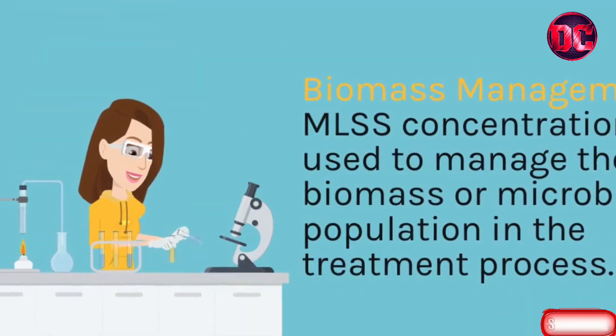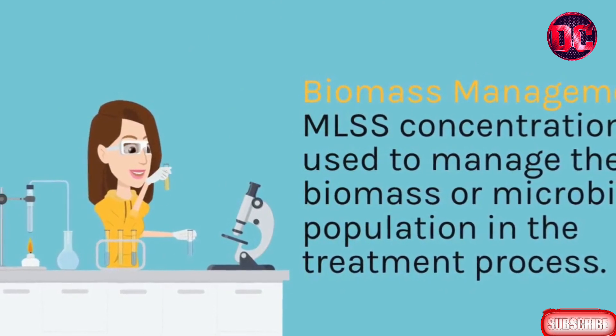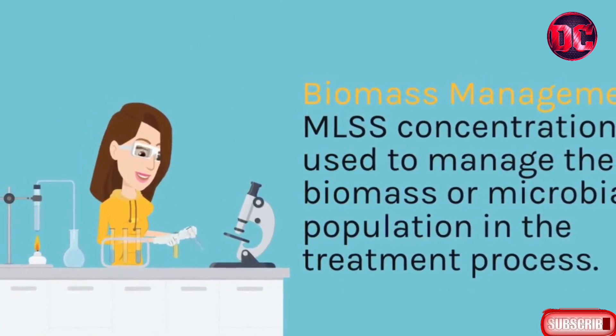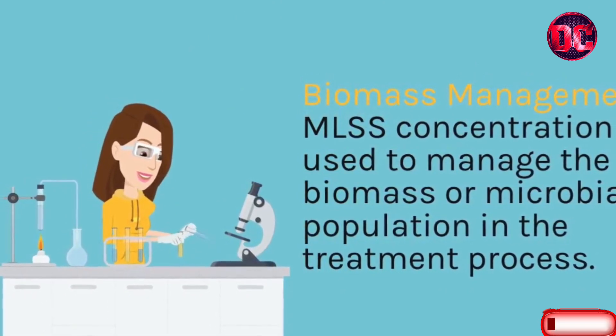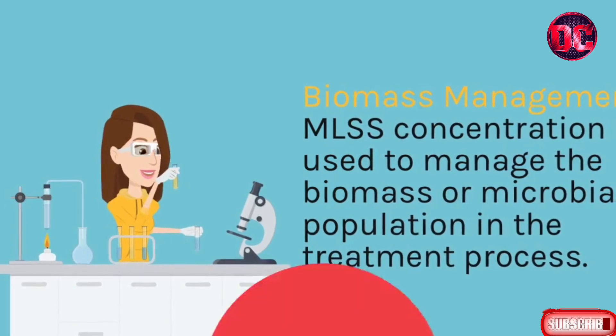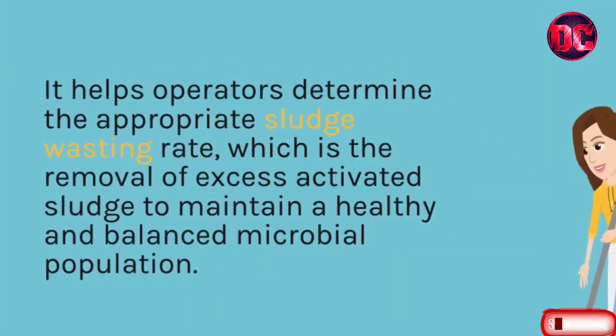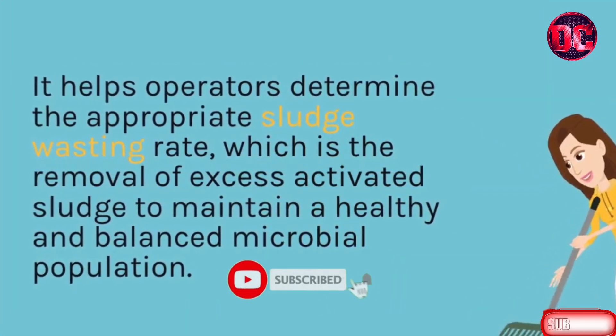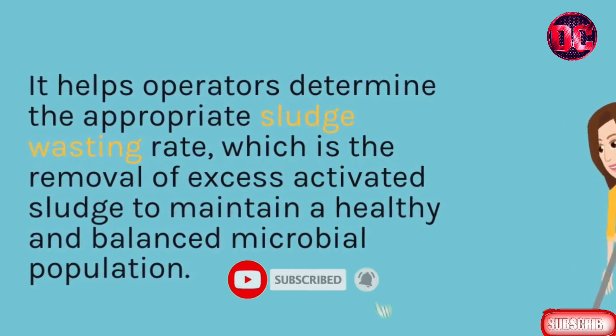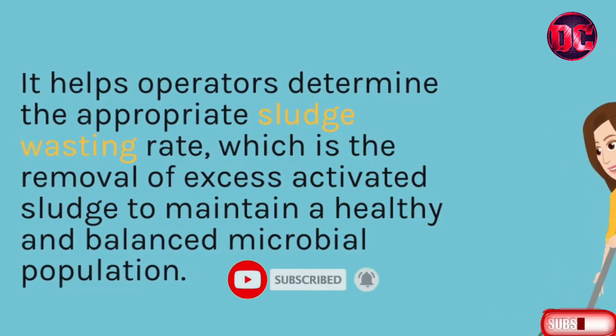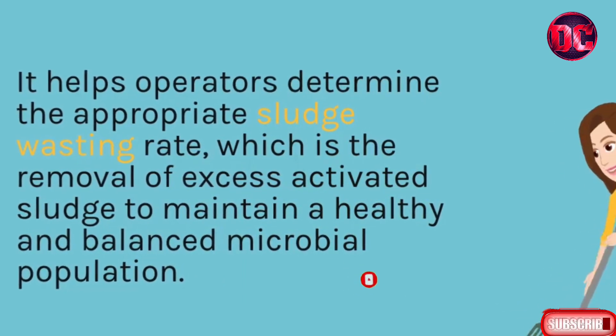MLSS concentration is used to manage the biomass, or microbial population, in the treatment process. It helps operators determine the appropriate sludge wasting rate, which is the removal of excess activated sludge, to maintain a healthy and balanced microbial population.